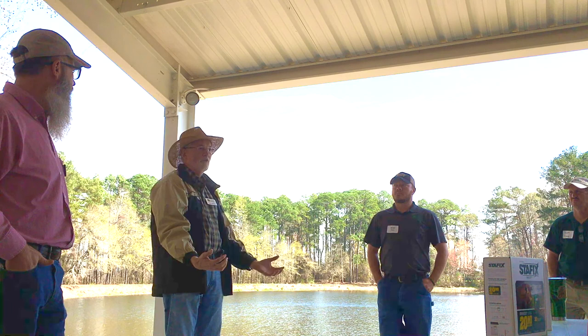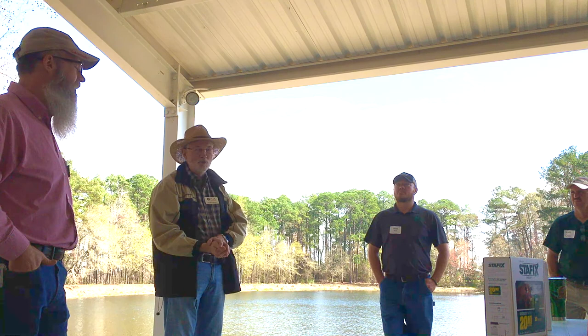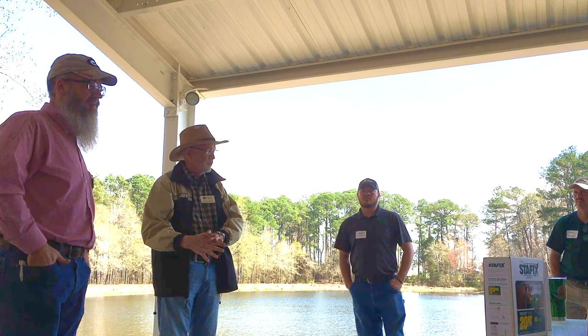So you're not going to stop lightning. What you have to do is provide a good path for it to go where you want it to go, which is not through the thing. So you need to have a better grounding field for your lightning protection than you've got for your charger.